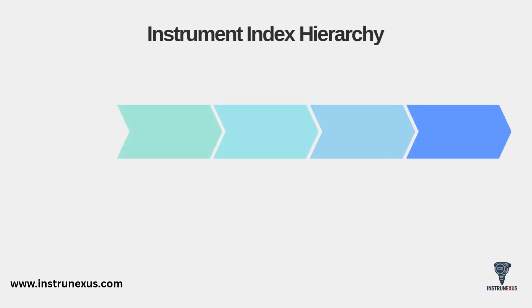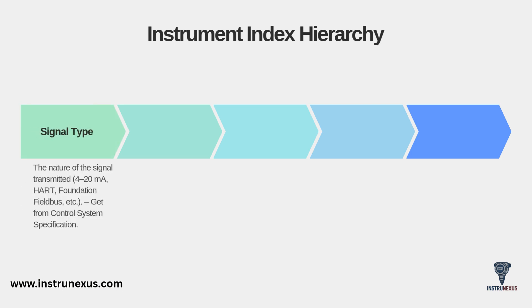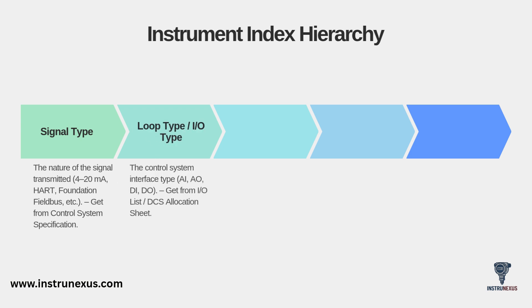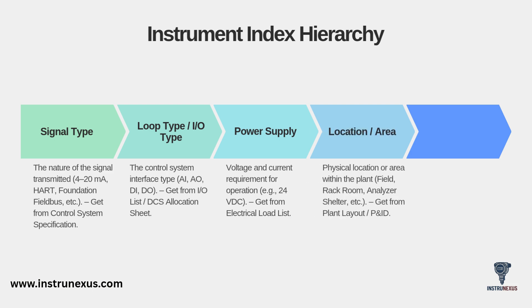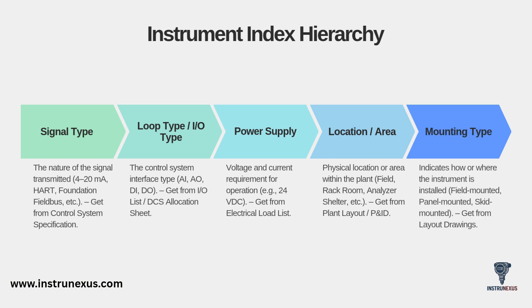The hierarchy continues by bridging the gap to the control and electrical systems. You must define the signal type: is it a 4–20 milliamp signal, is it using HART, or is it a digital signal like Foundation Fieldbus? This information comes from the control system specification. You'll also list the loop type or I/O type — like AI, AO, DI, or DO — which you get from the I/O list or DCS allocation sheet. Then comes the power supply requirement, such as 24 VDC, from the electrical load list. Finally, you specify the physical location or area, like field, rack room, or analyzer shelter, and the mounting type, such as field mounted or panel mounted.